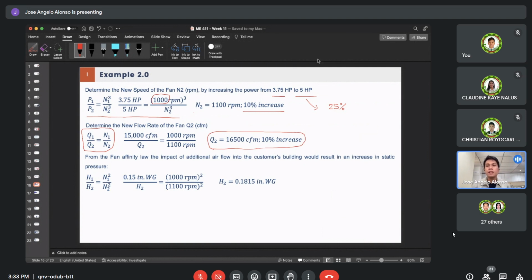So from a 25% increase in power, we got a 10% increase in volume flow rate, or fan capacity. Okay, then lastly, from the fan affinity law, the impact of additional airflow into the customer building would result in an increase in static pressure. So from 0.15 inch water gauge, our static pressure increased to 0.1815 inch water gauge.